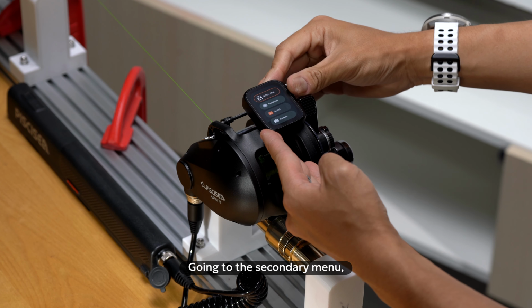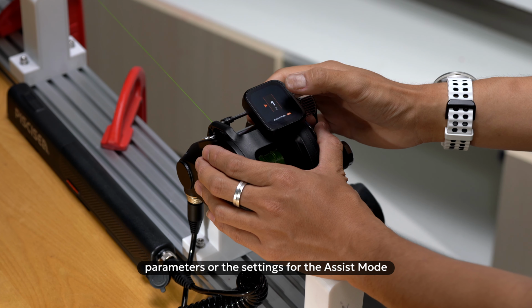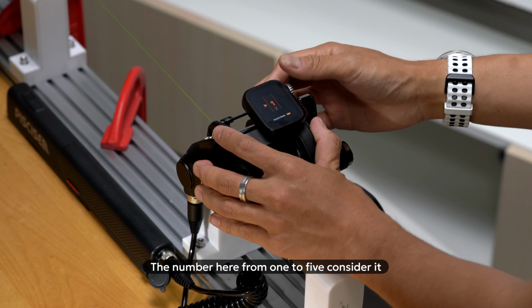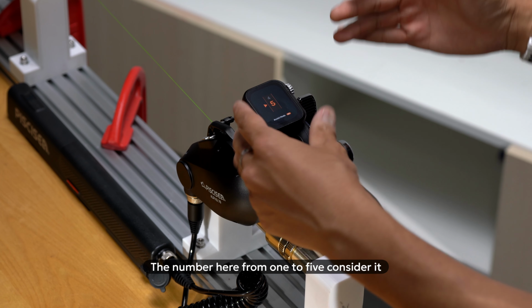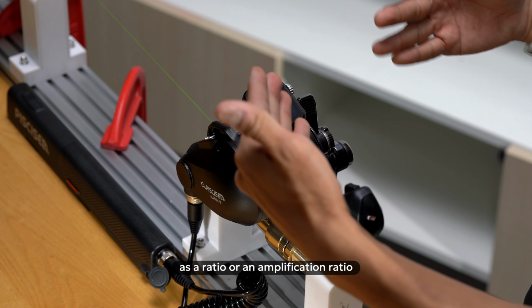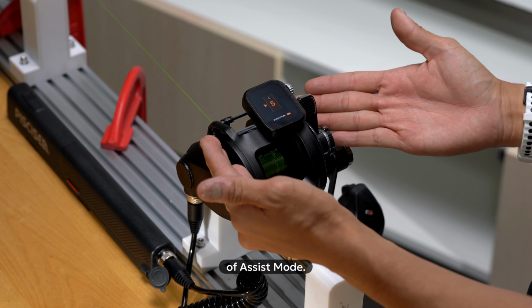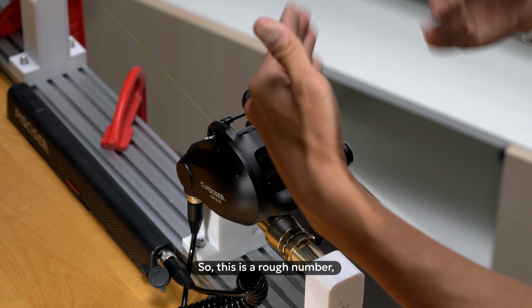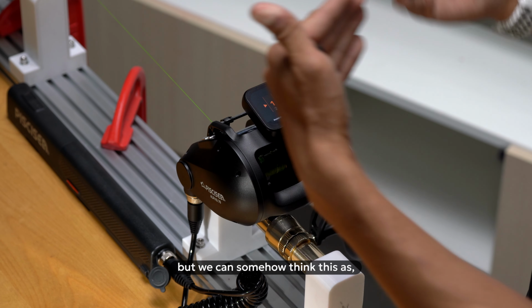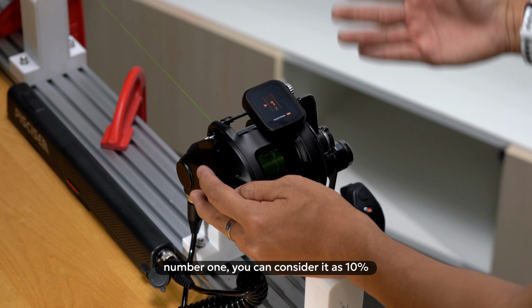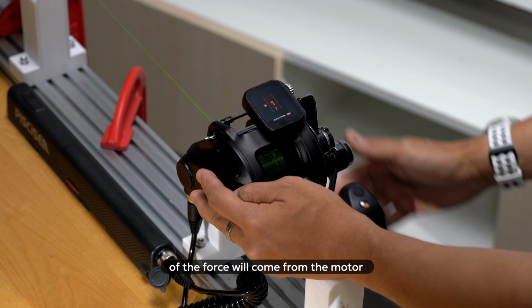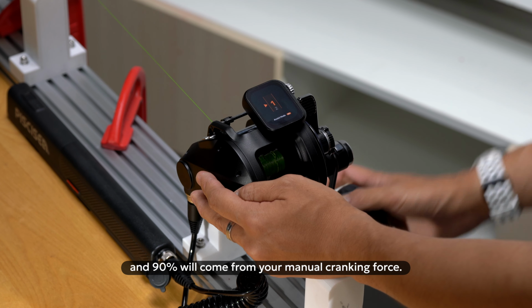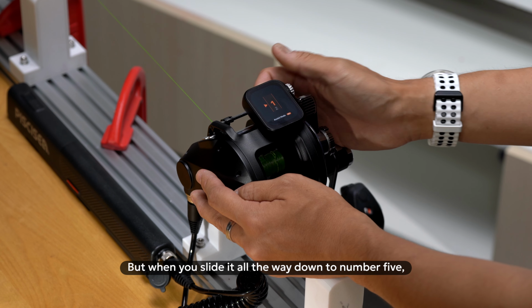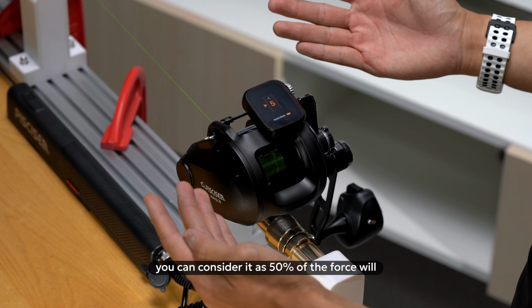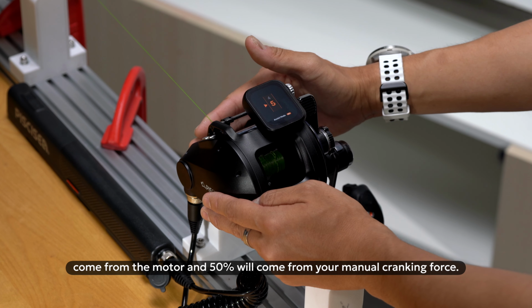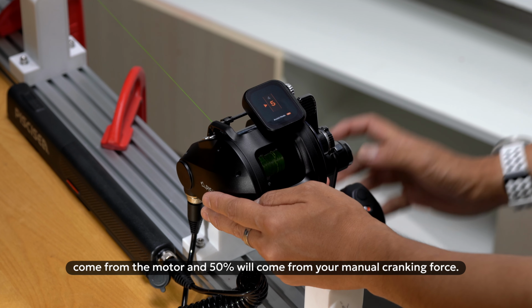Going to the secondary menu, you can also change the parameters or the settings for the assist mode. The number here from 1 to 5, consider it as a ratio or an amplification ratio of assist mode. So this is a rough number, but we can somehow think of number 1 as 10% of the force will come from the motor and 90% will come from your manual cranking force. But when you slide it all the way down to number 5, you can consider it as 50% of the force will come from the motor and 50% will come from your manual cranking force.